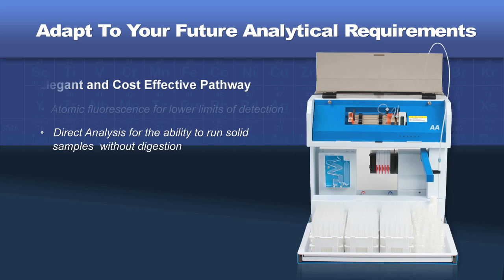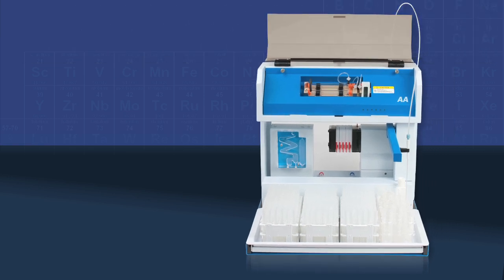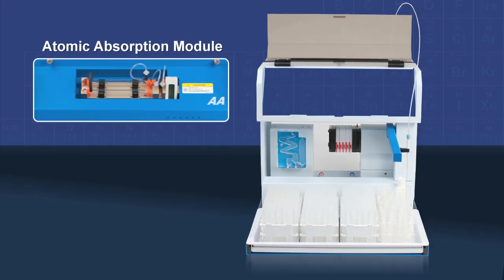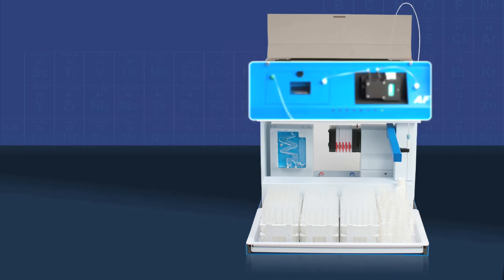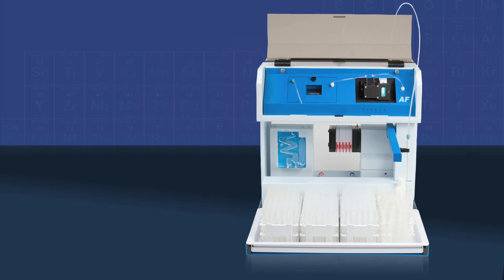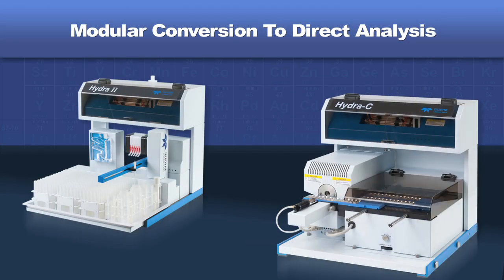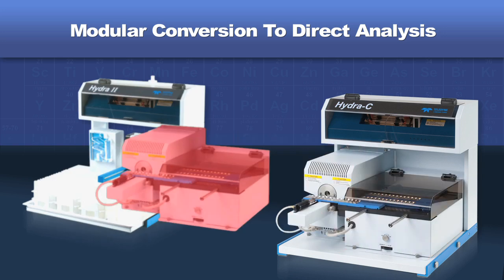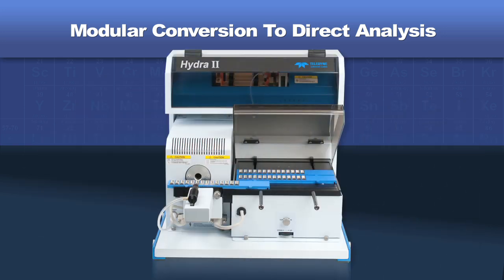The transition to atomic fluorescence involves simply replacing the atomic absorption module with the atomic fluorescence module. Similarly, for people who run into difficult-to-digest samples or prefer to avoid some sample digestions, Leeman Labs provides a modular conversion to direct analysis by thermal decomposition.